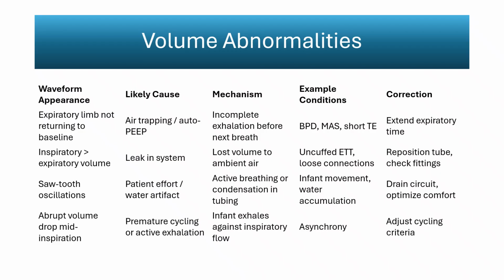Recognizing these abnormalities provides a direct assessment of exhalation adequacy, leak severity, and synchrony. Matching expiratory time to lung mechanics, correcting leaks, removing artifacts, and aligning the breath cycle with the infant's effort prevents air trapping, ensures accurate tidal volume monitoring, and improves overall ventilation stability.